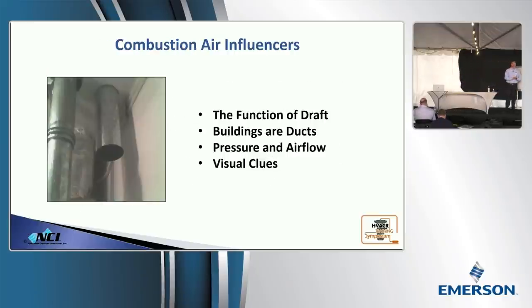Now, when we look at some influencers on combustion air, we run ducts vertically or horizontally, and we assume the air direction, right? That pipe that's coming through the ceiling there and is wide open, what do we assume that's going to do? We assume it's bringing in outside air, right? And guys, we're clever. Sometimes we will actually put labels on there, or we'll write it in a Sharpie, combustion air, and then we'll put an arrow. Like the air goes, oh, I've got to go down that one. I can't go down the other one. Air can't read a code book. Air can't read labels. We have to direct it because there are some things that drive it.